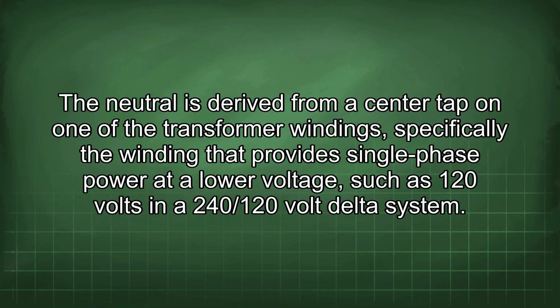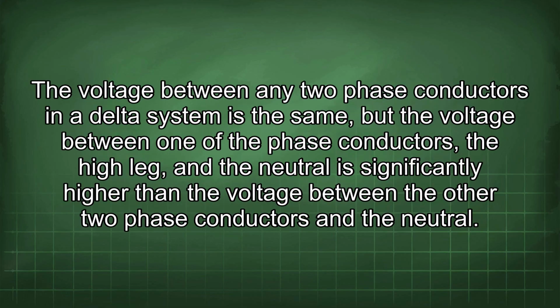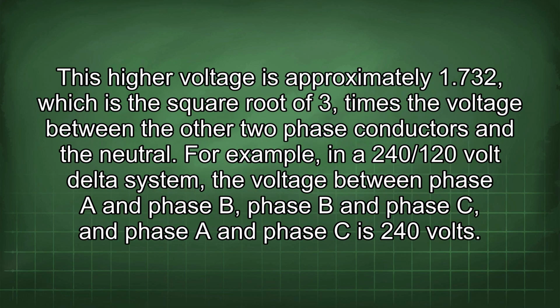240/120 volt delta system. The voltage between any 2 phase conductors in a delta system is the same, but the voltage between one of the phase conductors, the high leg, and the neutral is significantly higher than the voltage between the other 2 phase conductors and the neutral. This higher voltage is approximately 1.732, which is the square root of 3, times the voltage between the other 2 phase conductors and the neutral.